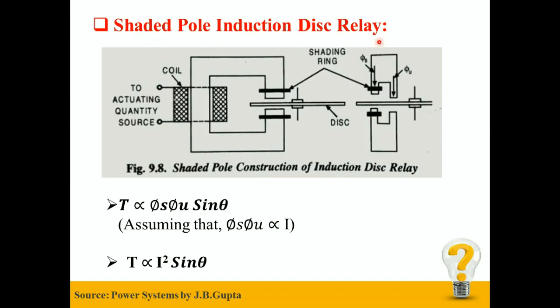Shaded Pole Induction Disc Relay: the shaded pole structure is usually actuated by current flowing in a single winding on a magnetic structure containing an air gap. The air gap flux produced is split into two fluxes that are displaced in time and space by shading rings, generally made up of copper, that encircles part of the pole face on each pole.